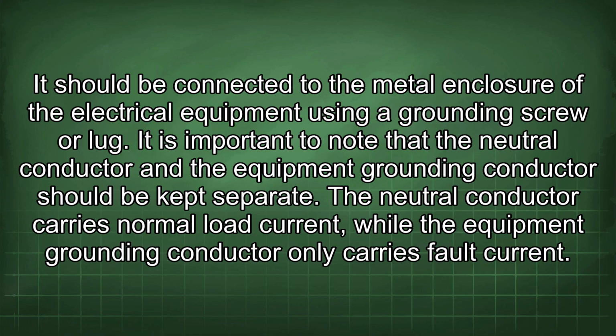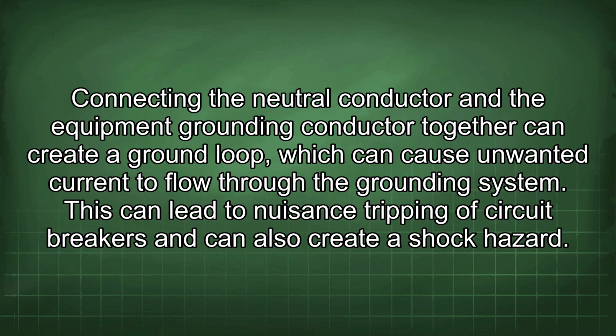It is important to note that the neutral conductor and the equipment grounding conductor should be kept separate. The neutral conductor carries normal load current, while the equipment grounding conductor only carries fault current. Connecting the neutral conductor and the equipment grounding conductor together can create a ground loop, which can cause unwanted current to flow through the grounding system. This can lead to nuisance tripping of circuit breakers and can also create a shock hazard.